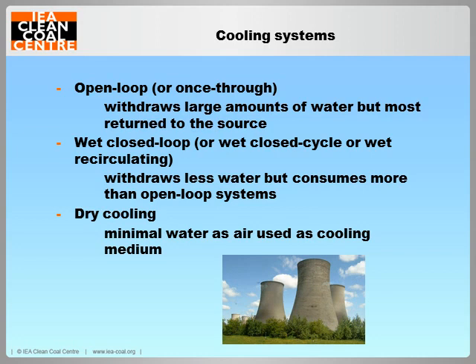Dry cooling systems use air instead of water as the cooling medium in the cooling tower, so they're better suited to dry regions. But they are the least attractive economically, as they can cost about 3 to 4 times more to build than a wet closed-loop system. And of course, they also lower the overall plant efficiency by about 2 to 7 percentage points, and this can be even higher on a hot day. This is because air is a less efficient cooling medium than water.